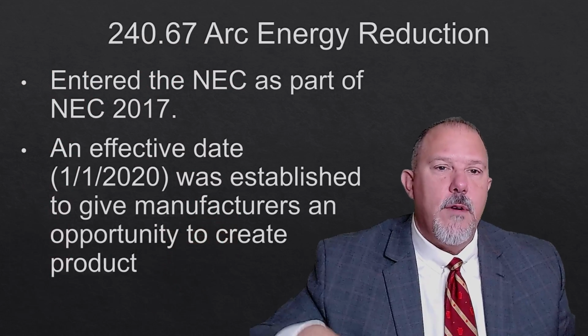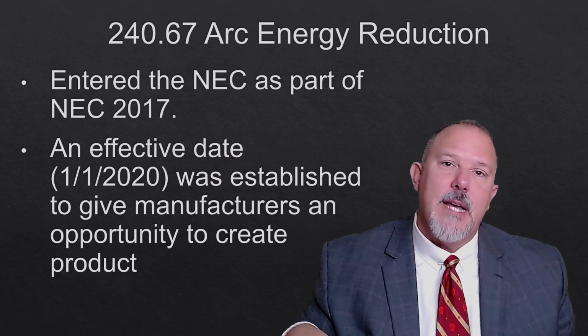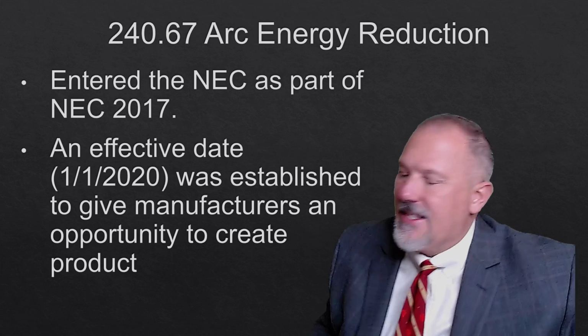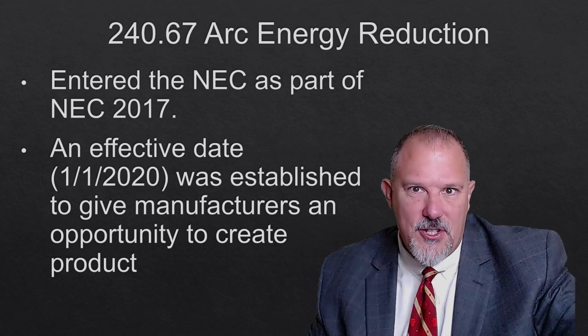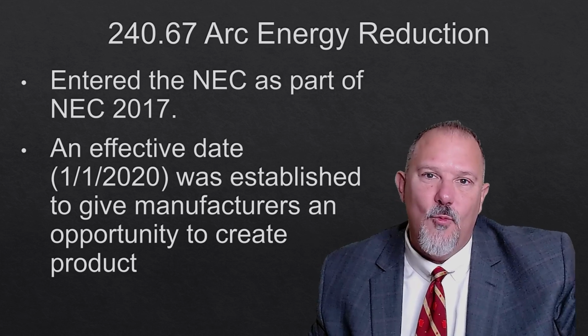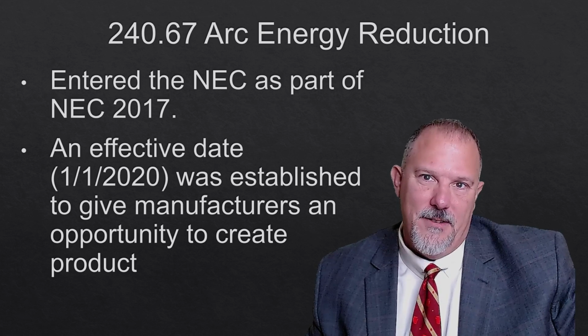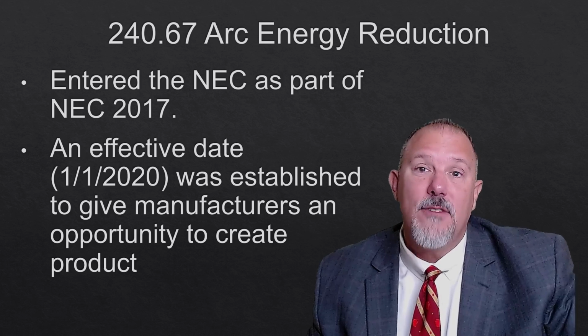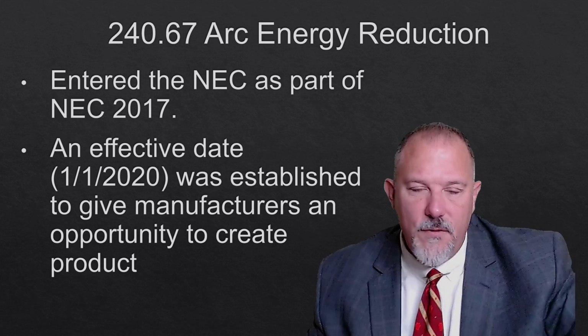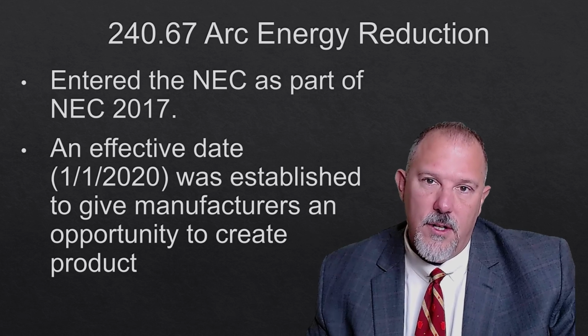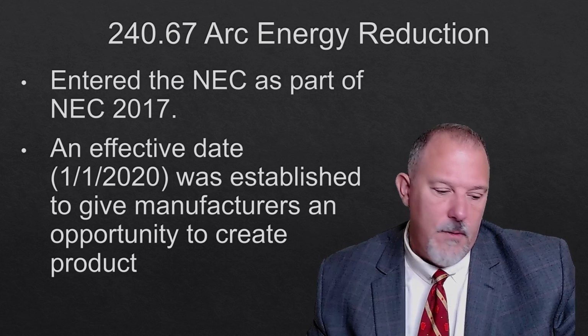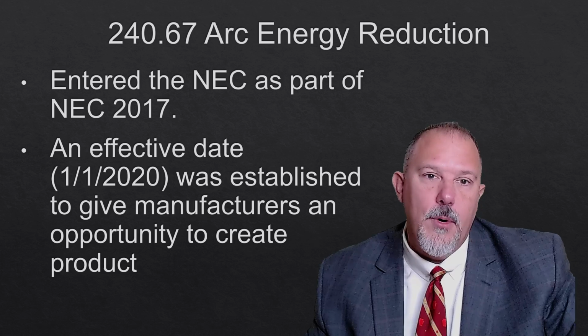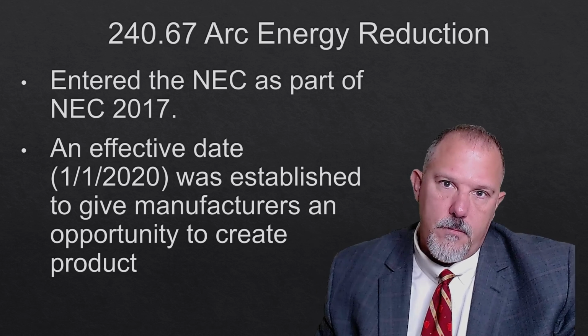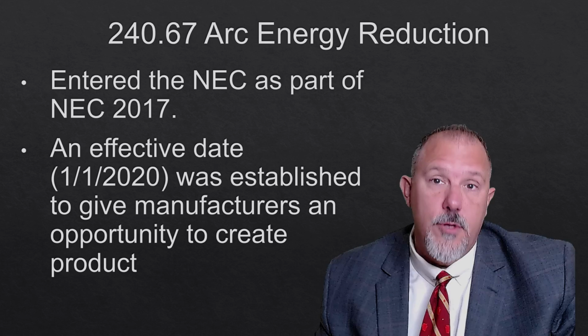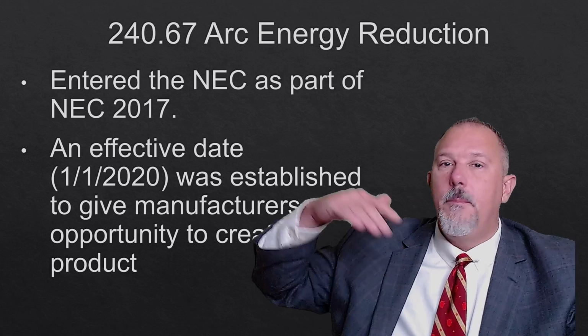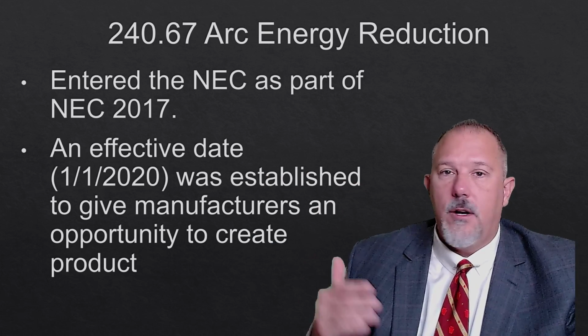Now, 240.67 entered in 2017. And what happened in 2017? They said, wait a second. Incident energy is not discriminatory on what overcurrent device it's under. What's protecting it? It's all about current and time. So someone said 240.67 fuses have a similar issue. So we had a code requirement put in for 240.67 for fusible applications to reduce incident energy when you've got the big fuses that are very similar to circuit breakers.